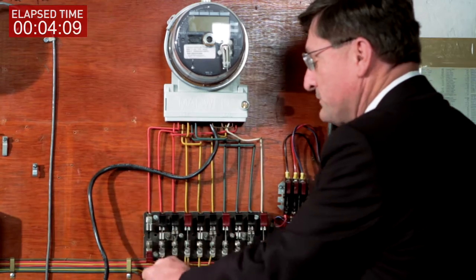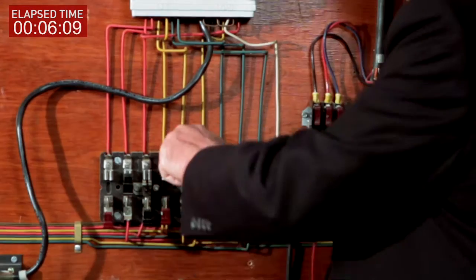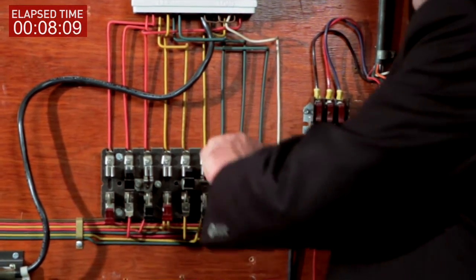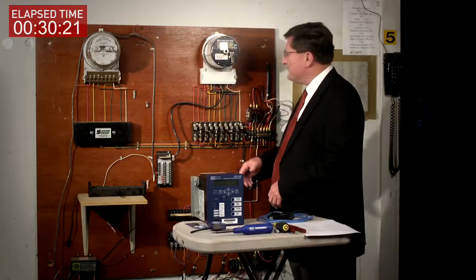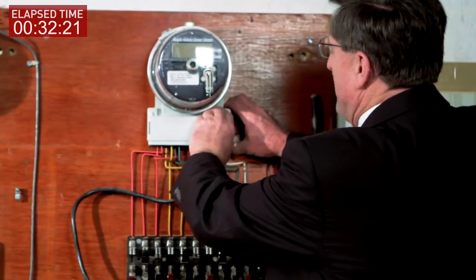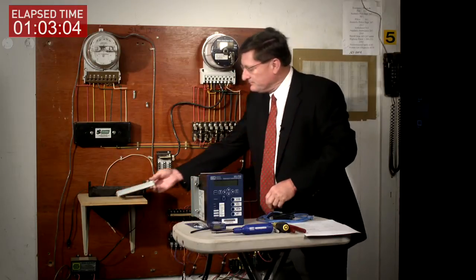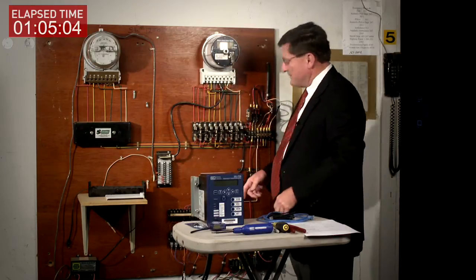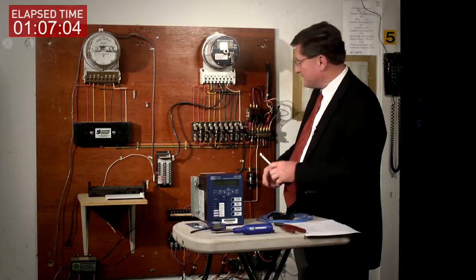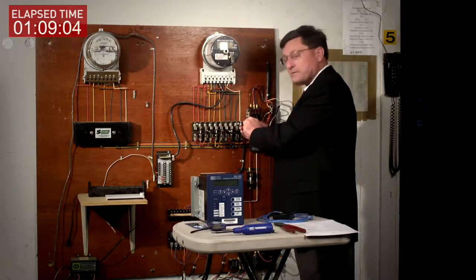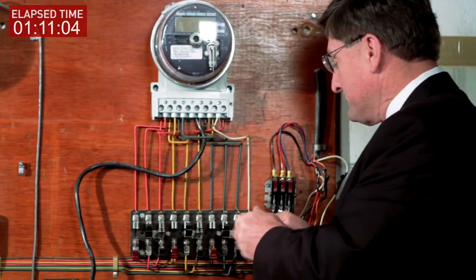We begin by removing the test switch cover, opening our test switches here to isolate the meter from your actual service. Next we'll remove our cover over our secondary connections. Now we're going to take our nut driver and remove our connections on the top of the meter test switch.